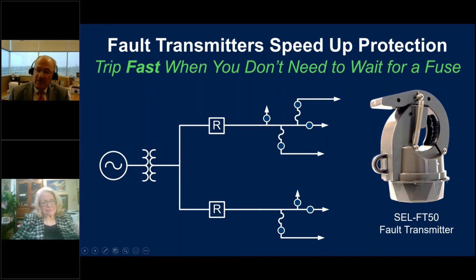Well, these little fault transmitters, which are a little bit bigger than a coffee cup, clamp onto the conductor. You install it with a hot stick. There's no batteries in it. It takes its power from the power line, from the current, and fires up a little transmitter that sends out an encoded message whenever fault current goes through here. So you put these out at various points like the blue dots show, and now if you get a signal from this main line fault transmitter back here to the relay, guess what?